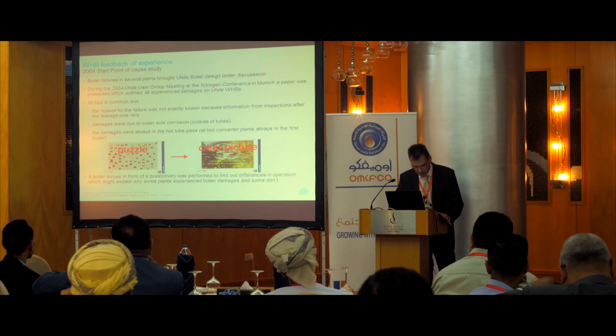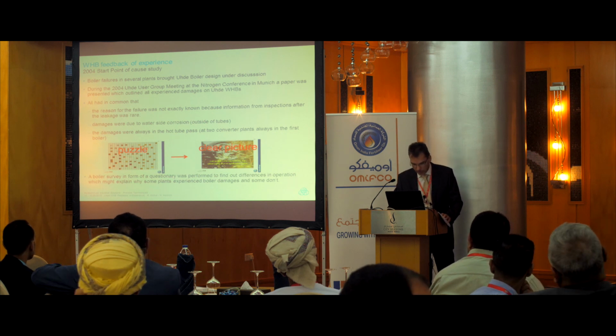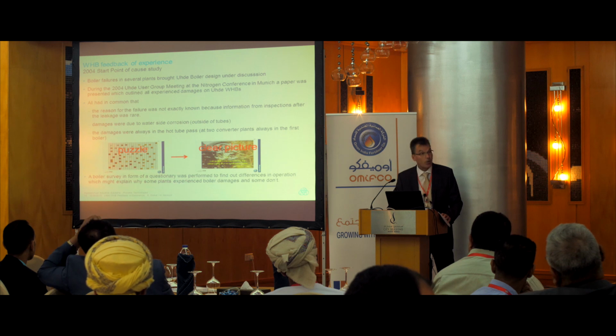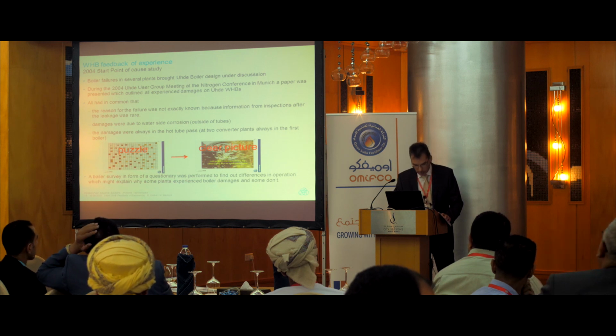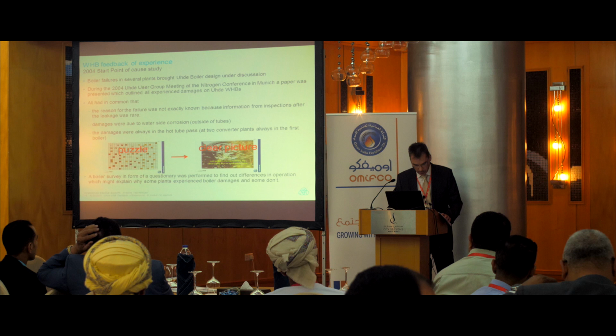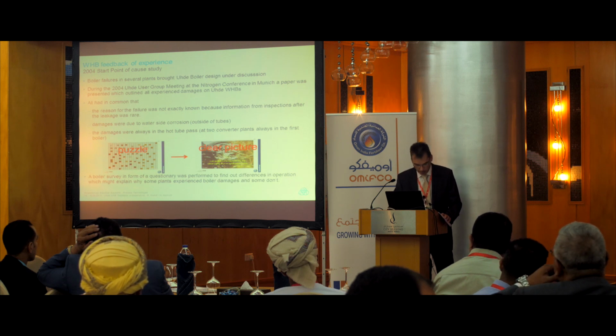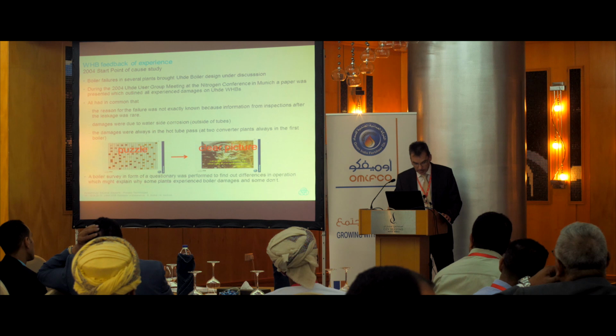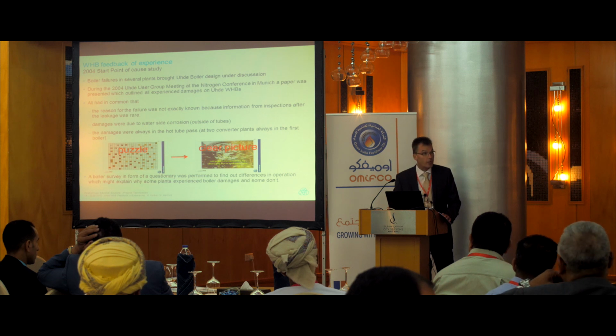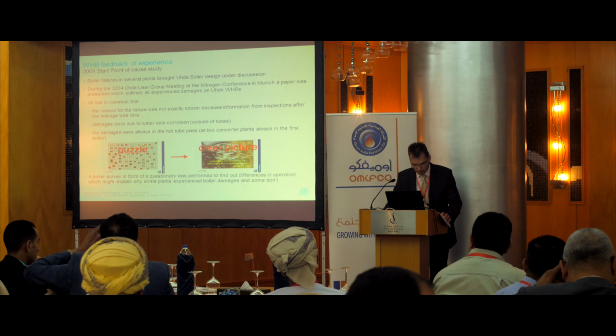At the beginning of the 90s, leaks were experienced in several waste heat boilers, in single converter and also in 2 converter plants. The information available was very rare. Sometimes only the leaking tube was known, but not the exact location. Sometimes the leak location was near the tube sheet. Sometimes the leak was located in a support baffle location. But all had in common that the leak was due to loss of wall thickness from the outside. This opened the field of discussion.